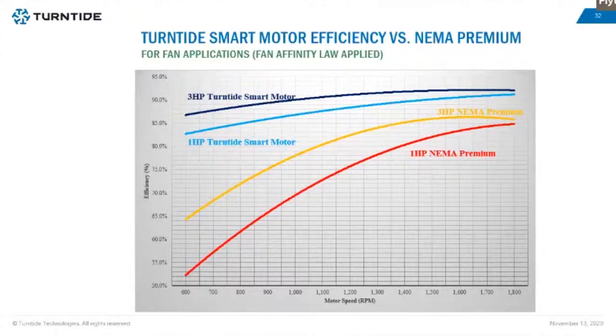The point I'm trying to make is that even though you can get a high efficiency induction motor, that's only at the rated condition. When you apply it to a fan, applying the cubic relationship, you can see what happens when it is running at 1/3 the speed. Instead of 1500 RPM or 1800 RPM, it runs at 500 RPM or 600 RPM, and it's 1/27 the power. Efficiency is almost 30% lower.